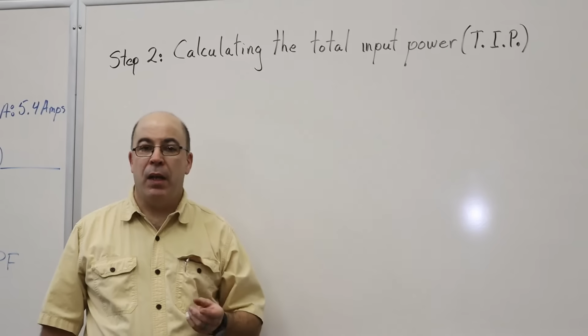Now, to make things a little bit easier, I'm going to move down onto this other board and just keep moving along. Now, our next step is going to be to calculate the total input power. That means that now that I've done the conversion from horsepower to watts, I have to allow for the efficiencies of the motor.